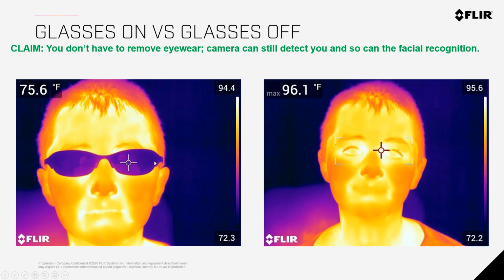When he takes those glasses off, right again at the inner canthus of the eye, we see he's 96.1 degrees Fahrenheit. So IR detectors cannot see through glass. They can't see through a window, eyeglasses, bifocals, sunglasses, work goggles, or rec specs. They can't see through any of that material. An IR detector or sensor will hit that material and bounce off almost like a mirror, like us brushing our teeth in the morning, looking in the bathroom mirror.